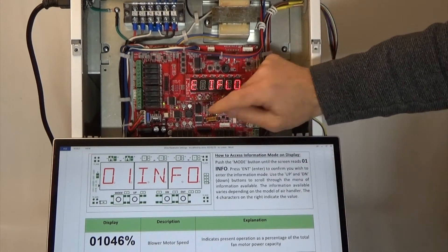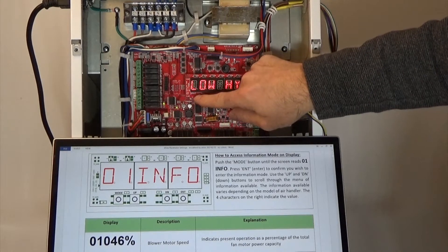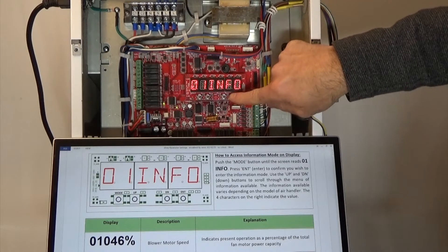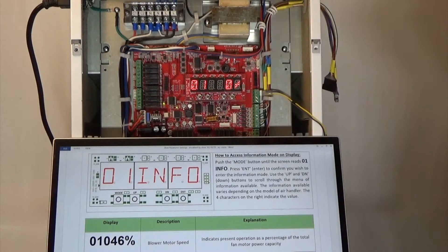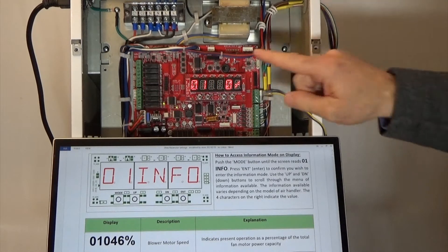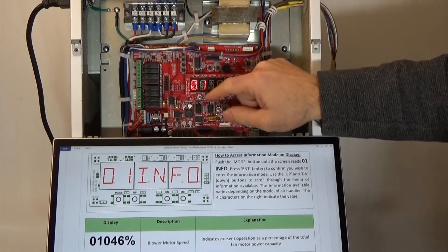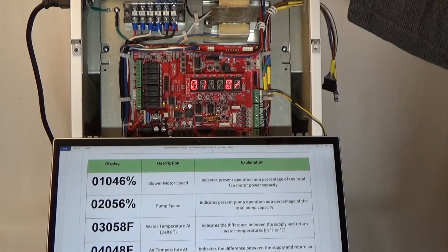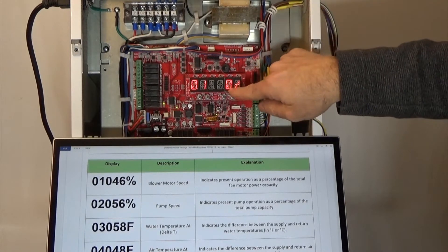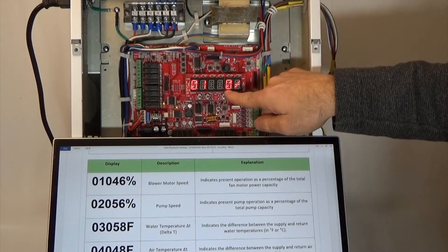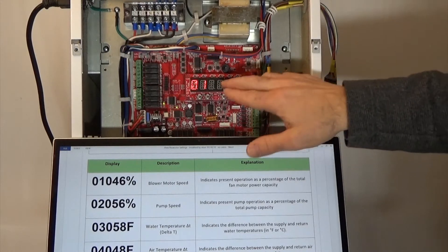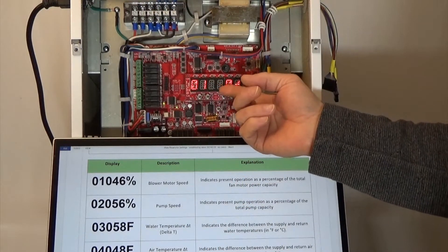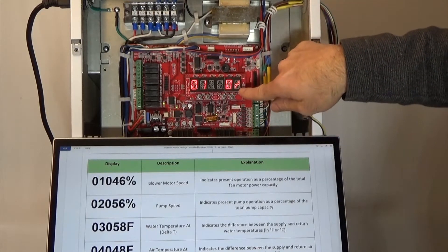If we go into information mode, we press the mode button once — that's information — then we press enter on the right to enter into information mode, and we have parameter number one. Parameter number one in information mode is the blower speed. The unit is off, so it's saying the blower speed is 0%. If the blower was operating at 20% or 30%, you would see that percentage here. This little icon represents percentage.